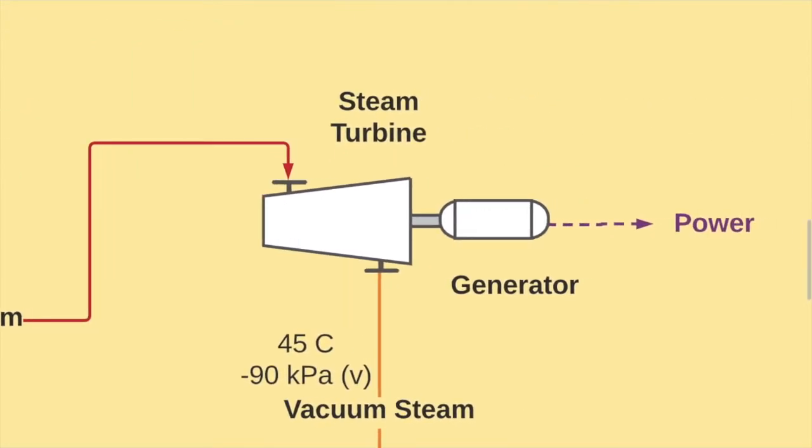On to the turbine. The high-pressure steam flows through a set of fan blades towards the outlet of the turbine, which is at a very low pressure. Here, the outlet pressure on our turbine is at 90 kPa of vacuum. A large, modern turbine is around 90 percent efficient for converting heat into work as the pressure is reduced. Our turbine extracts 9.6 megawatts of power and produces a fog with about 10 percent water. The turbine spins the generator and we extract 9.1 megawatts of electrical power.